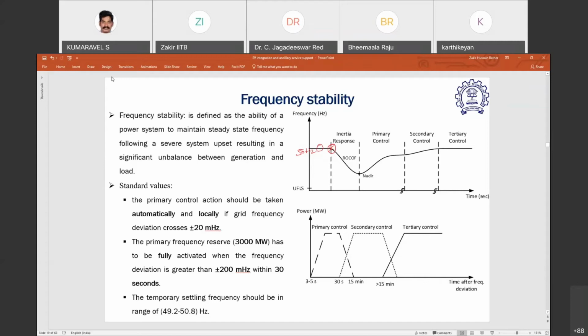What did I say earlier? The fundamental requirement of stable, secure grid operation is that at each and every instant, the generation and load must balance. Now, those who are not familiar with this, look carefully here, pay attention. How do things happen at the onset of the disturbance? Once the disturbance takes place, we lose the generation, 500, 800 megawatt, whatever capacity. Load is not going to change. Load is the same. Now what should change? Ideally, the generation should change. But for the generation to change, to match the load or to match the deficit of the lost generation, it will take its own sweet time.